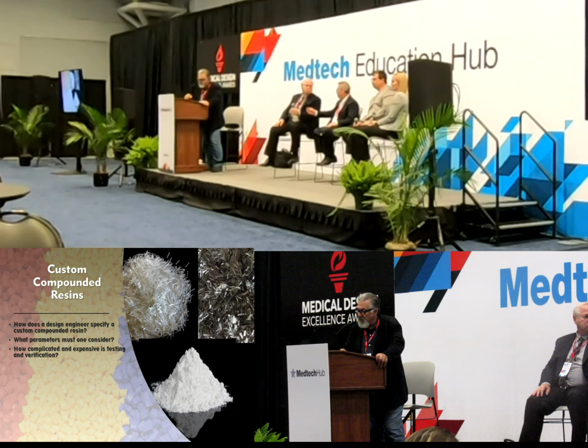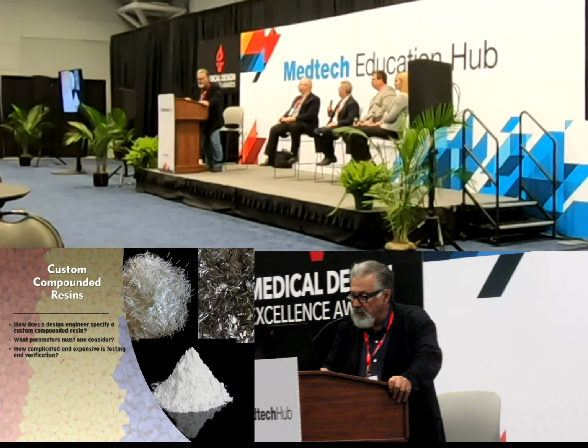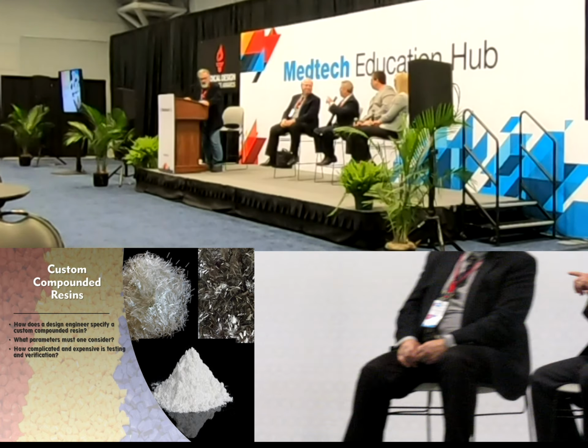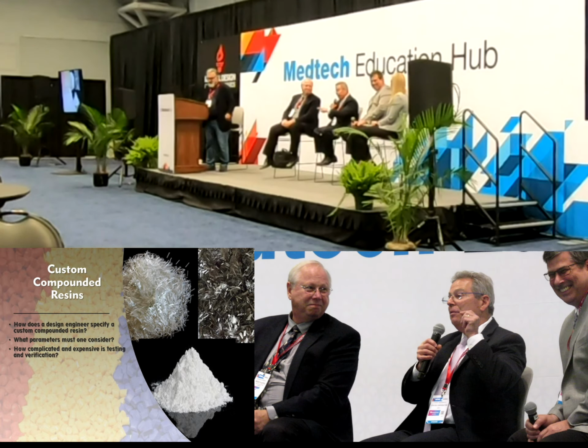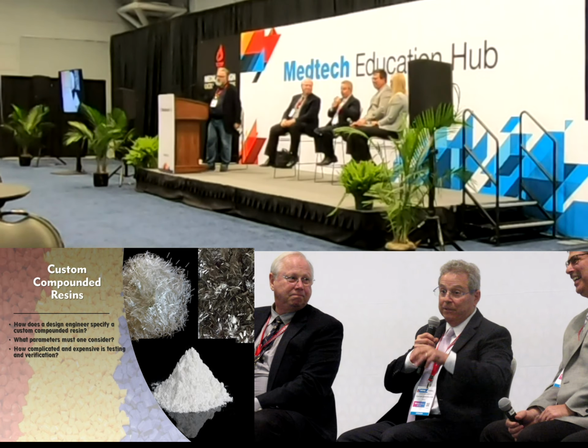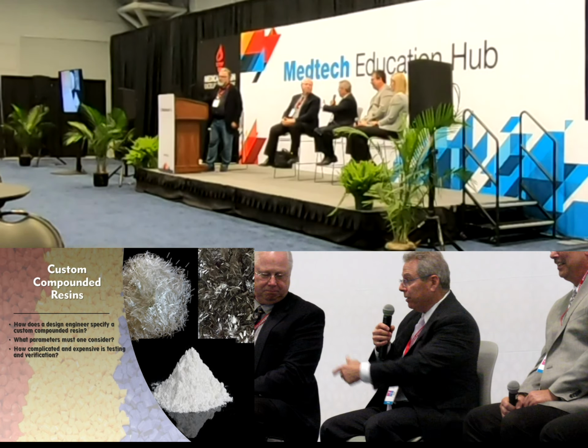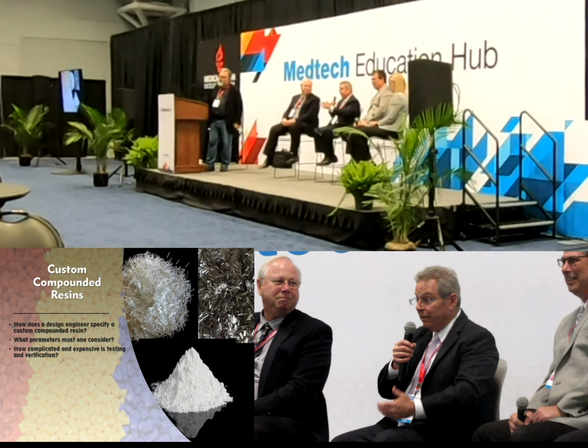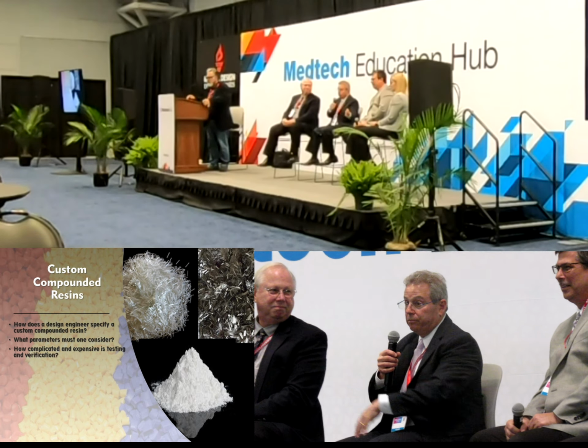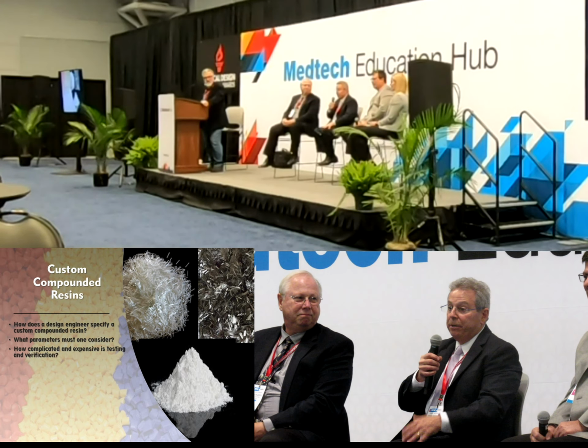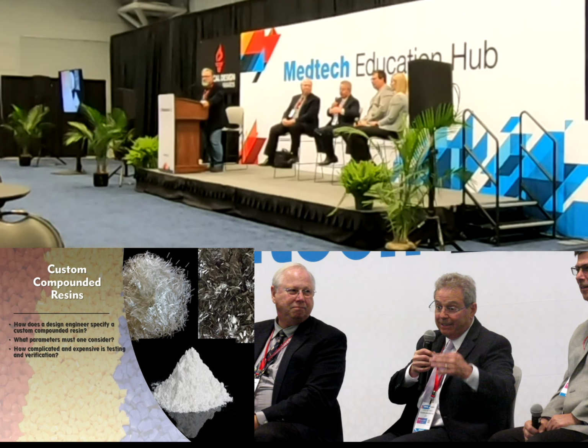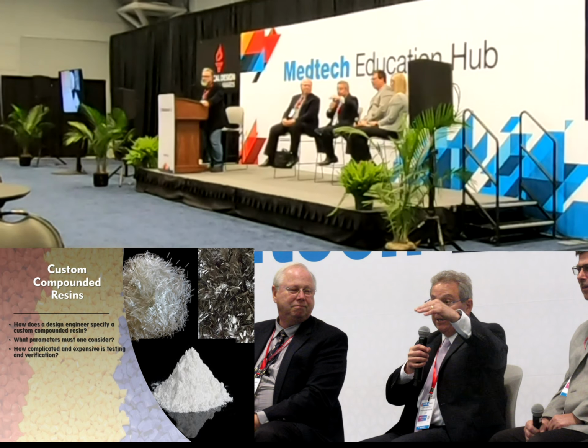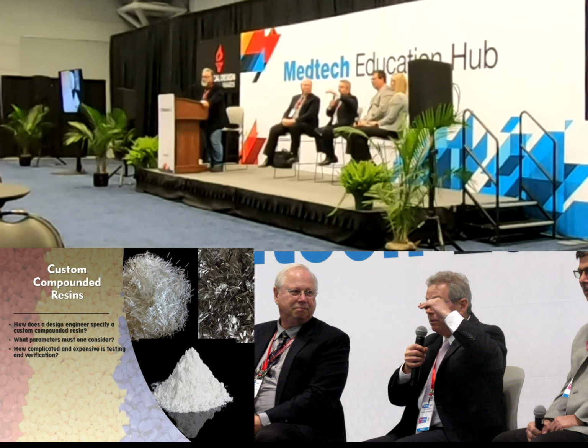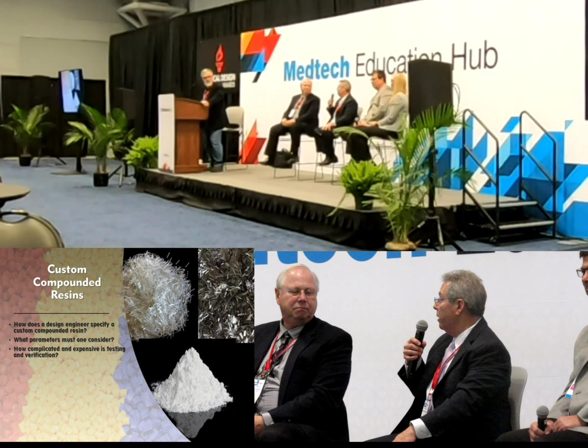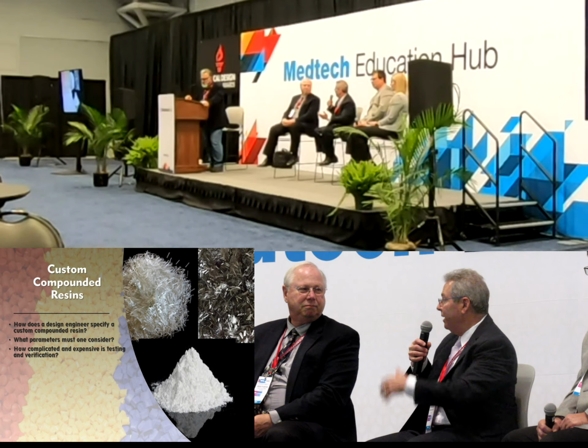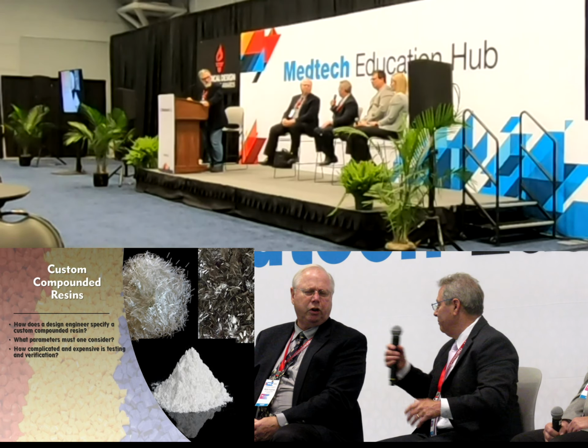Thank you very much. We have probably time for one or two more slides. One more quick comment on that: it's very dependent on where it's going. If it's outside the body, very, very quickly. If it's inside the body for less than 7 days, you've got a little more of a regulatory pathway. If it's going to be in for greater than 7 days up to 30 days, the steps get a little greater. Above 30 days, that puts you in a different category, permanent implant, and that's where the time comes in.